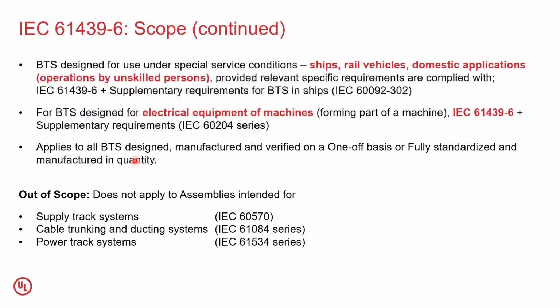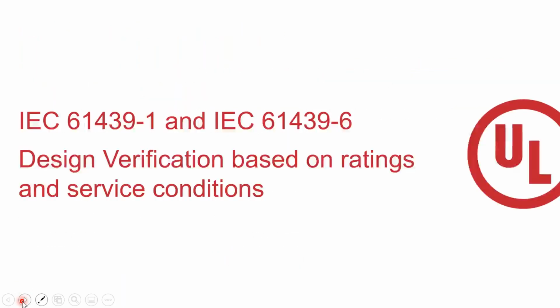The 61439-6 applies to all of the bus trunking systems which I told you about in the previous slide, which are either designed or manufactured on a one-off basis or fully standardized, depending on the need. There are certain specific busway systems which are out of scope for this standard. For example, the supply track systems, the ones people use for lighting and similar applications, are not covered by this standard. You will have to apply 60570. For cable trunking and ducting systems, you need 61084, and for power track systems, we will need to apply the 61534 series. So these are clearly out of scope for this type of construction.